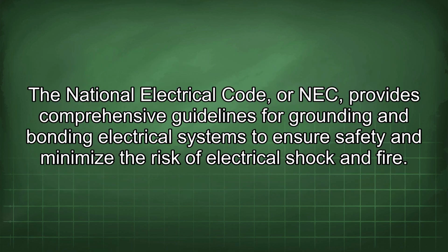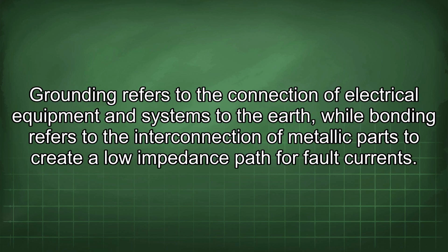The National Electrical Code, or NEC, provides comprehensive guidelines for grounding and bonding electrical systems to ensure safety and minimize the risk of electrical shock and fire. Grounding refers to the connection of electrical equipment and systems to the earth, while bonding refers to the interconnection of metallic parts to create a low impedance path for fault current.